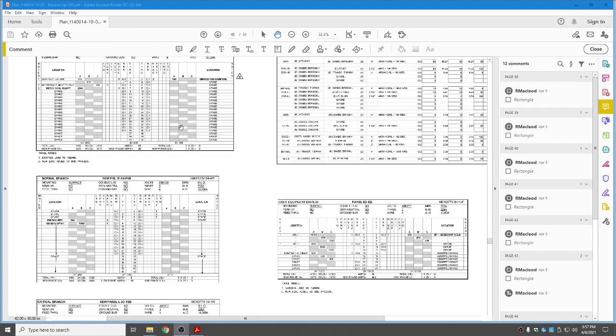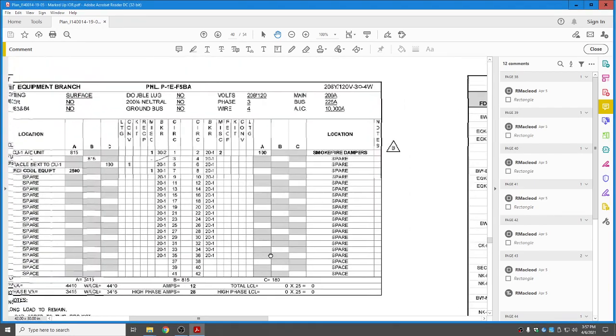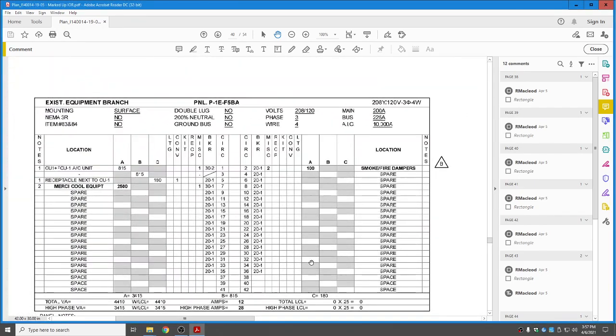On this page, you can see we have some panel boards. Let me zoom in. There's panel P1E, F5BA, and we had taught you earlier how to read the header here. It gives you all kinds of information you'll need to know. 208, 120 volt, 3-phase, 4-wire. The main is a 200 amp and the bus is rated at 225 amp.